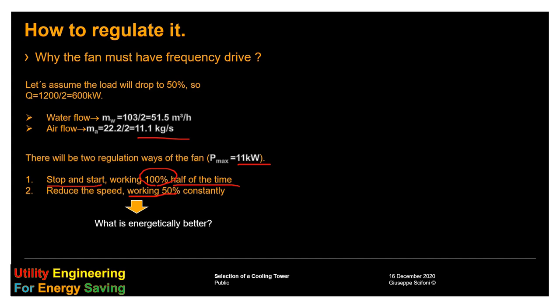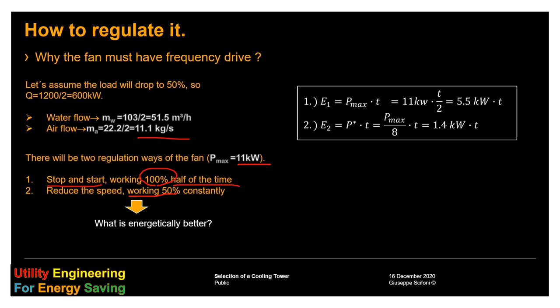What is energetically better? In the first case, the power is the maximum, but the time is the half. We get 5.5 kW times operational time. In the second case, the time will be the same, will be the full time, but the power is 1/8 of the maximum power. Eventually, we get 1.4 kW times operational time.